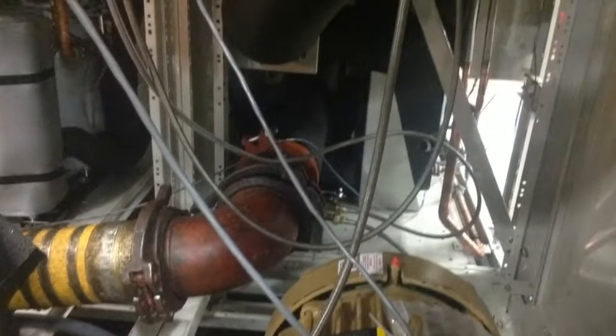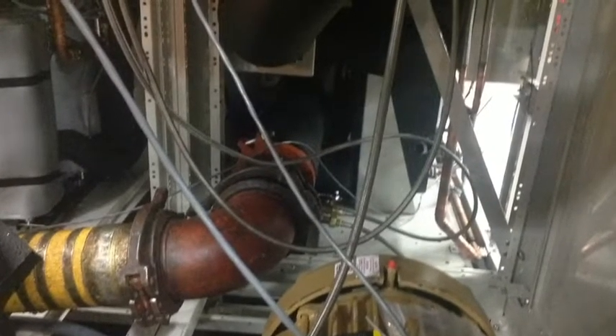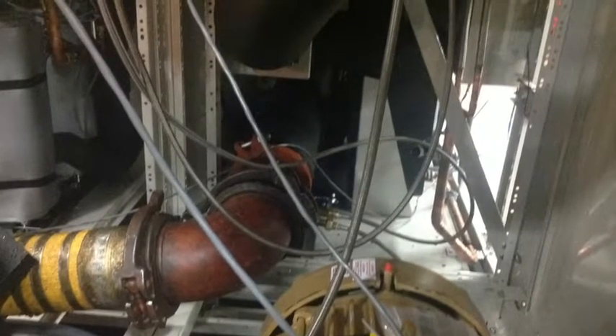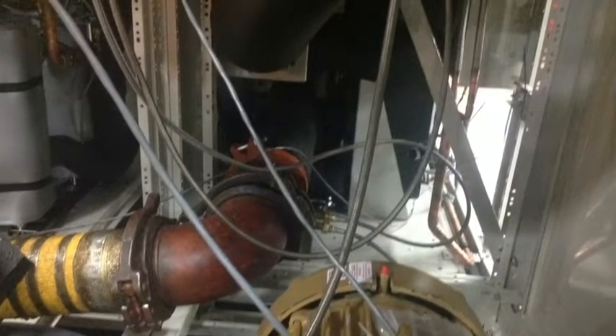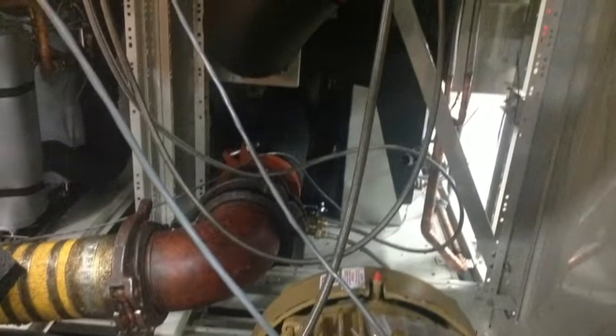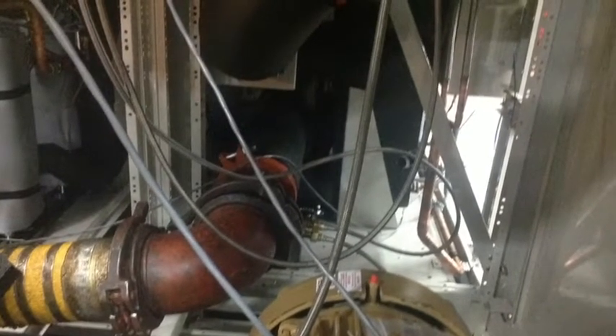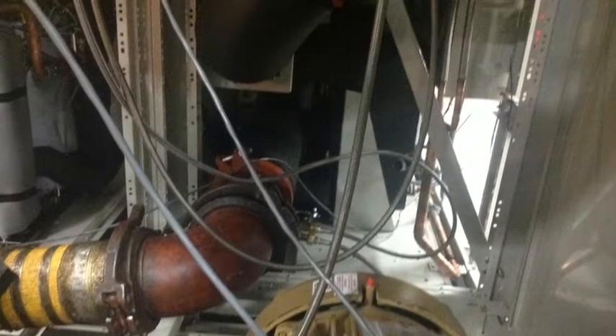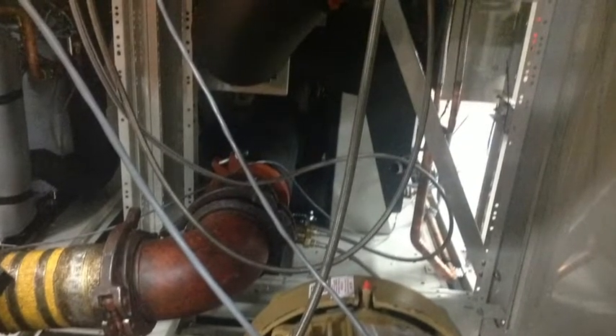You'll notice beyond the elbow that the braided hoses are connected to approximately a 6-inch spool piece of piping. It is this piping that we are making and shipping to the job site to allow you to connect the differential pressure transmitter input braided hoses.